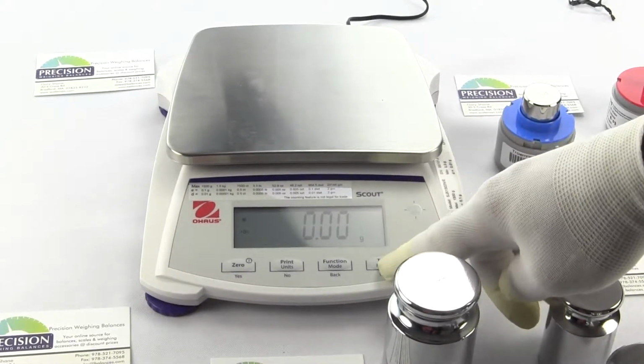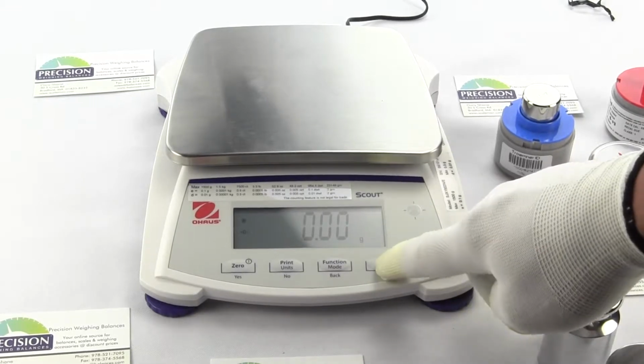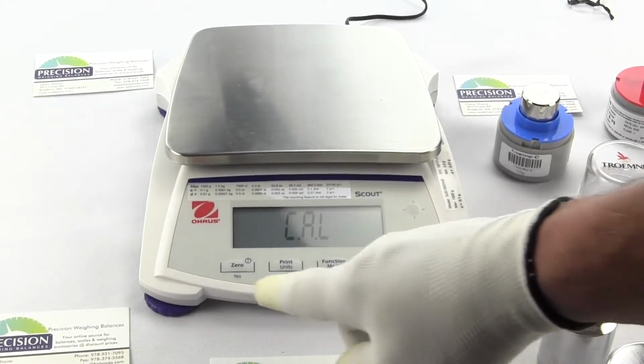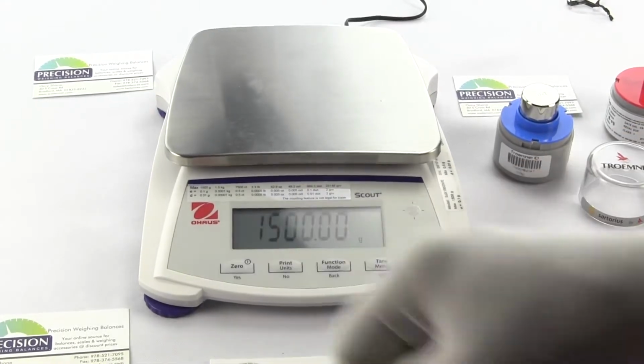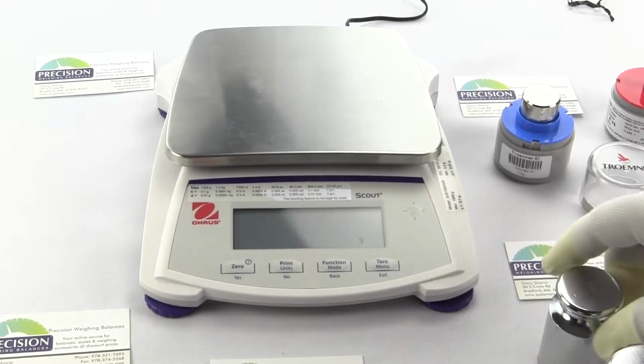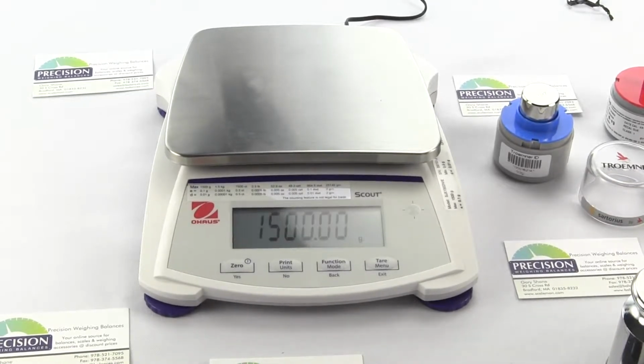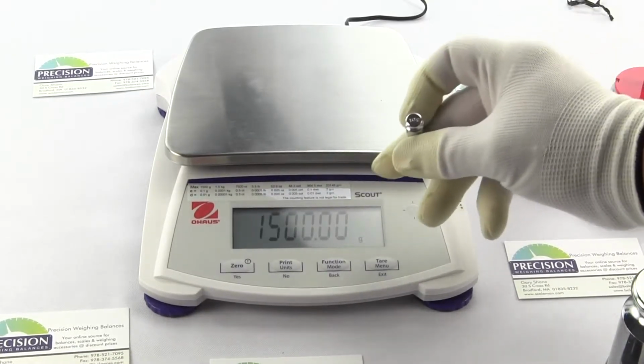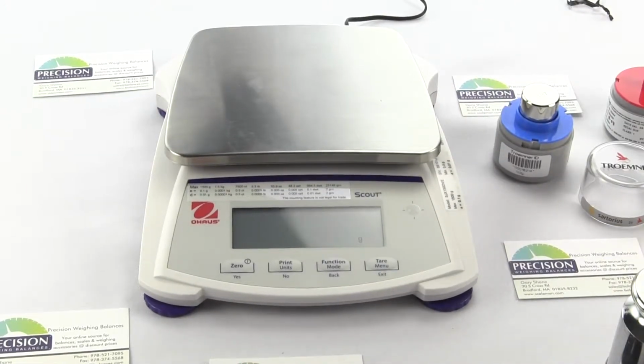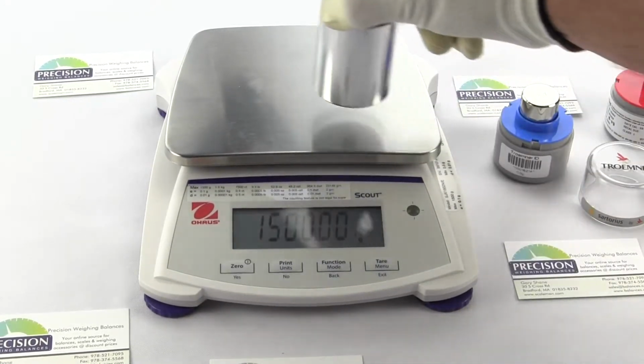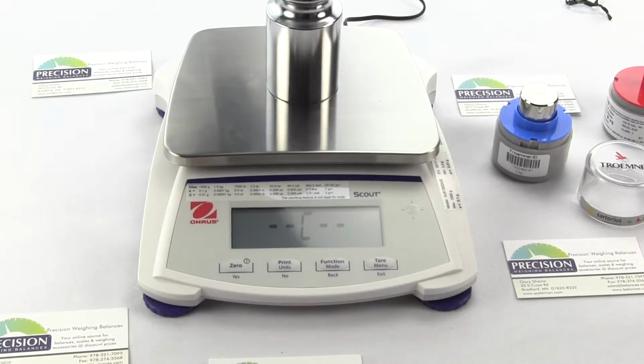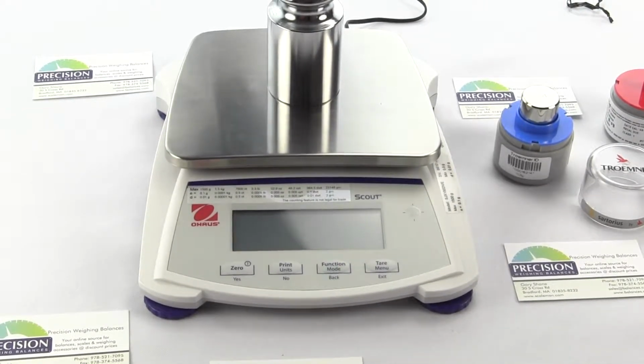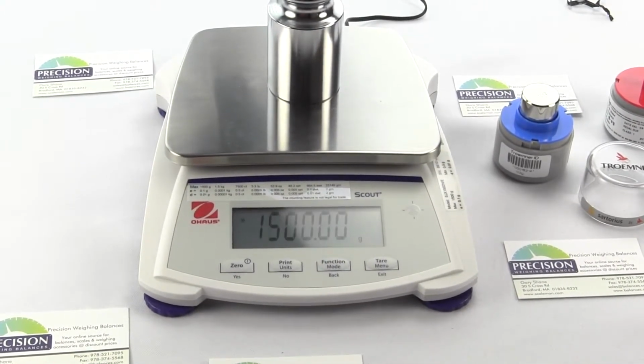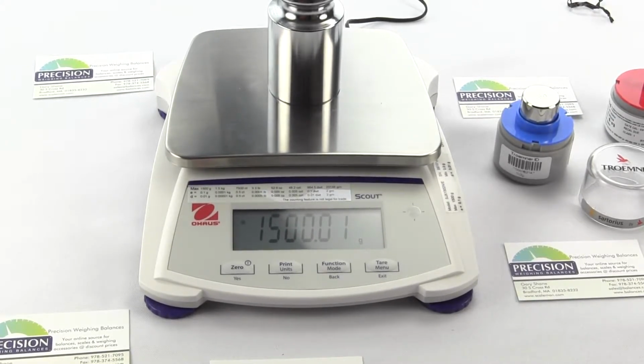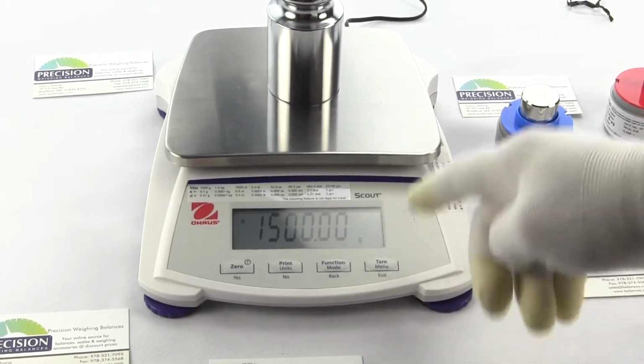So we'll go into the cal mode again. Simply press and hold the menu key. When you see menu, we have cal. Press span. We'll do a span calibration. The default again asks for 1500. This time, what I'm going to do is put 1500 with an extra 10 grams, so it's actually 1510. The scale will store it. It says done. Now it's going to display it as 1500.